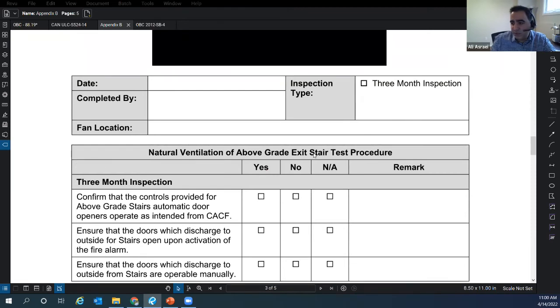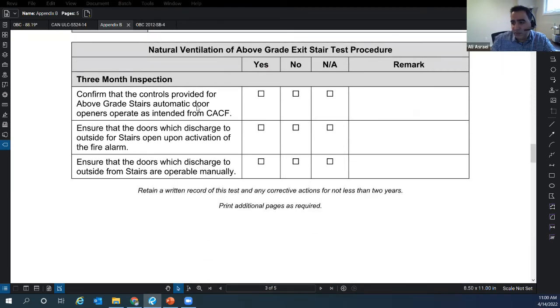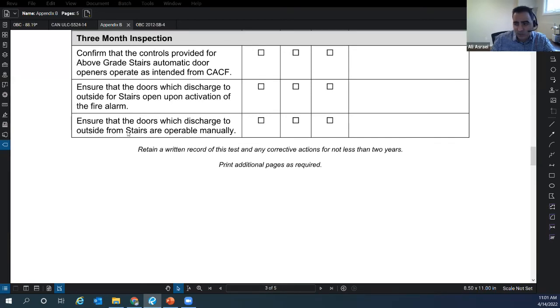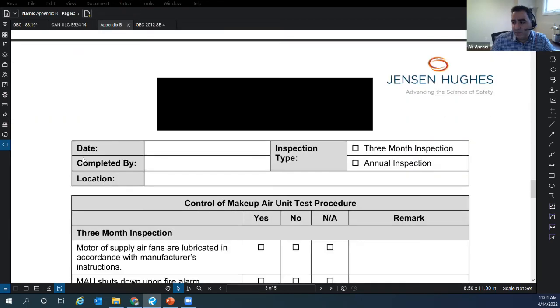This is for natural ventilation above grade. Controls provided for above grade stairs, automatic door openers operate as intended from the CACF room. Ensure the doors which discharge to outside of the stair open upon activation of the fire alarm. This building had an automatic door opener, but it could be different when we're dealing with a different building. Ensure that the doors which discharge to outside from the stairs are operable manually. So even though you can open it automatically, you have to be able to open them manually as well.